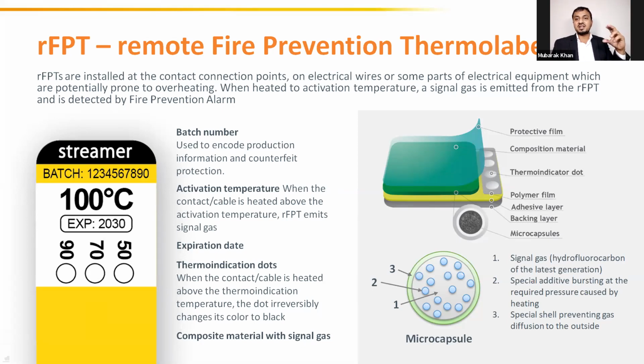When this sticker is installed on the joints as explained in the previous slide, when the temperature of the joint reaches 50 degrees Celsius, the 50 degree dot will change its color from white to black. When it reaches 70 degrees Celsius, the 70 degree dot will change its color from white to black irreversibly. When it reaches 90 degrees Celsius, the 90 degree dot will change its color from white to black irreversibly.